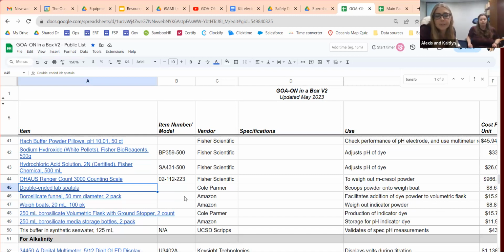And then, of course, down at the very bottom here is the tris buffer, coming straight from the Dickson lab at Scripps Institution of Oceanography, that has a known pH depending on temperature. So there's a table to reference depending on what the temperature of your tris buffer is, to then be able to measure the pH, and you can double check your spec pH measurements using that reference material. You can make tris buffer yourself, or a lab can. There are recipes in a paper, but we provide the tris buffer that's already made up because it's a lot simpler to do that and to know the value that the lab is ascribing to it.